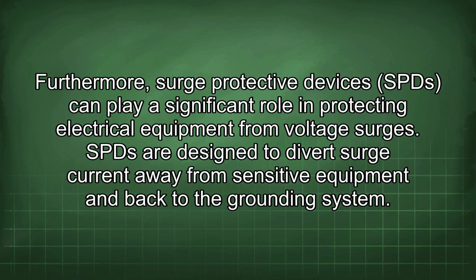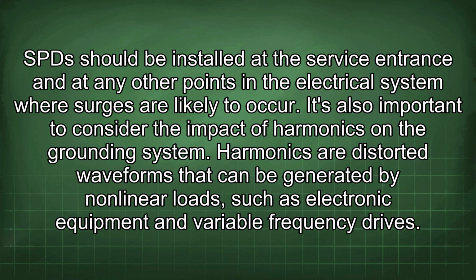Furthermore, surge protective devices (SPD) can play a significant role in protecting electrical equipment from voltage surges. SPD are designed to divert surge current away from sensitive equipment and back to the grounding system. SPD should be installed at the service entrance and at any other points in the electrical system where surges are likely to occur.